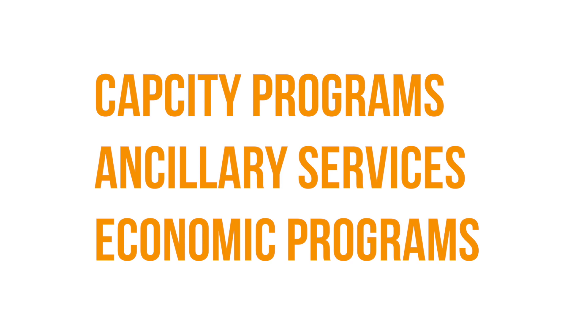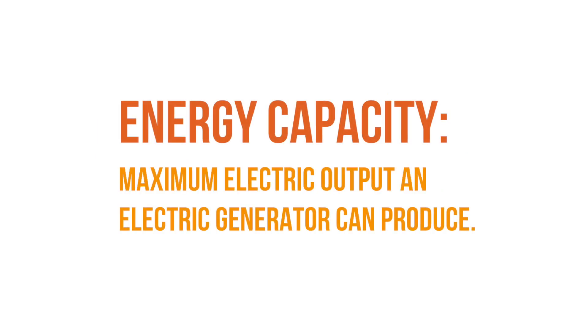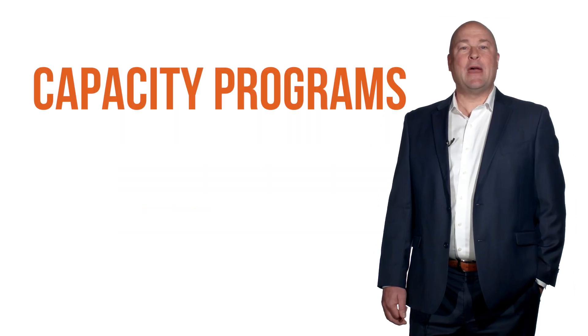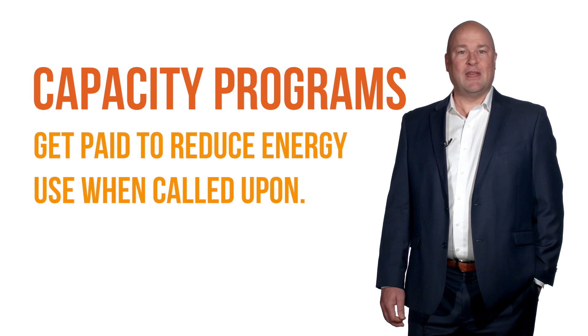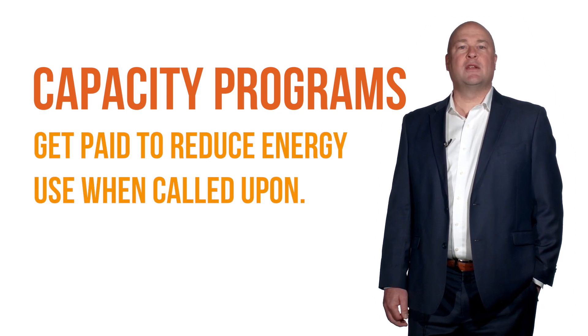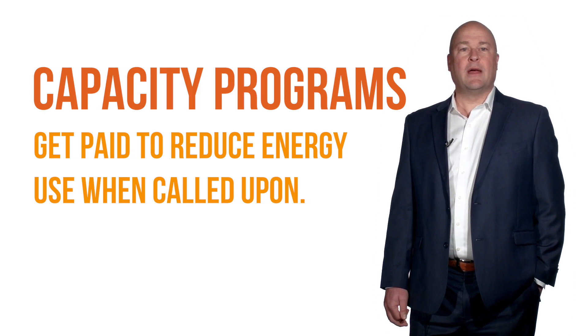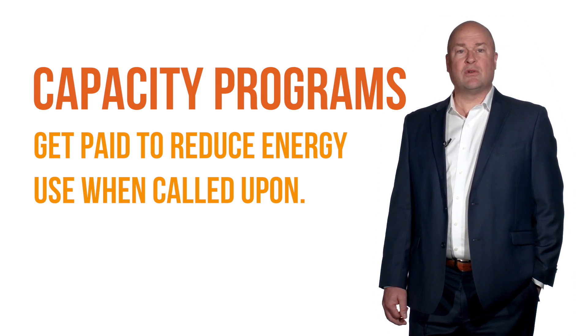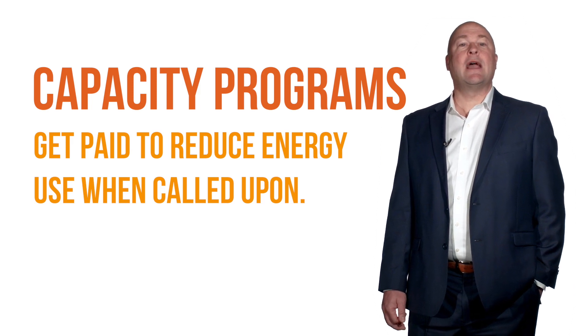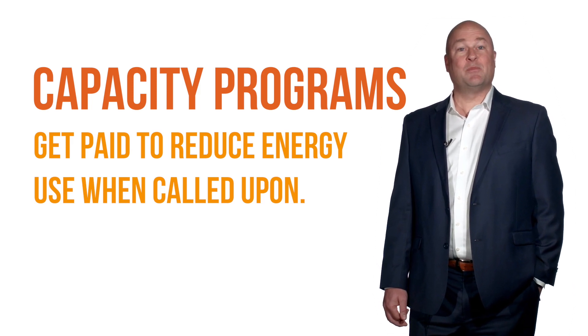Capacity, ancillary services, or economic. Capacity, as it relates to energy, is defined as the maximum electric output an electric generator can produce under specific conditions. Capacity programs are the backbone of demand response. They help create long-term grid stability by paying organizations to be on reserve to curtail their electric load when called upon by the grid operator to relieve stress when the demand for electricity outpaces the grid's ability to supply it.